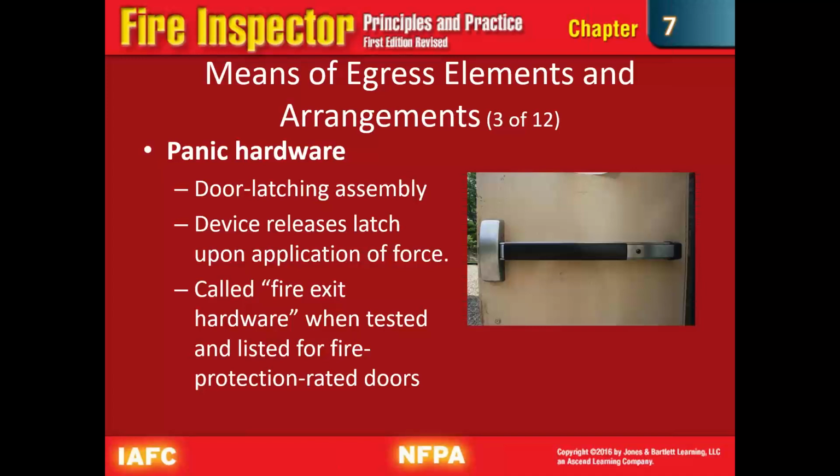And here we go, panic hardware, just like what I was talking about. It's a door latching assembly, and even if the door is locked, it can be opened from the inside. They call it panic hardware because you don't have to do anything but push against that little bar, and it opens up the door and allows it to be swung out so that the people can escape.